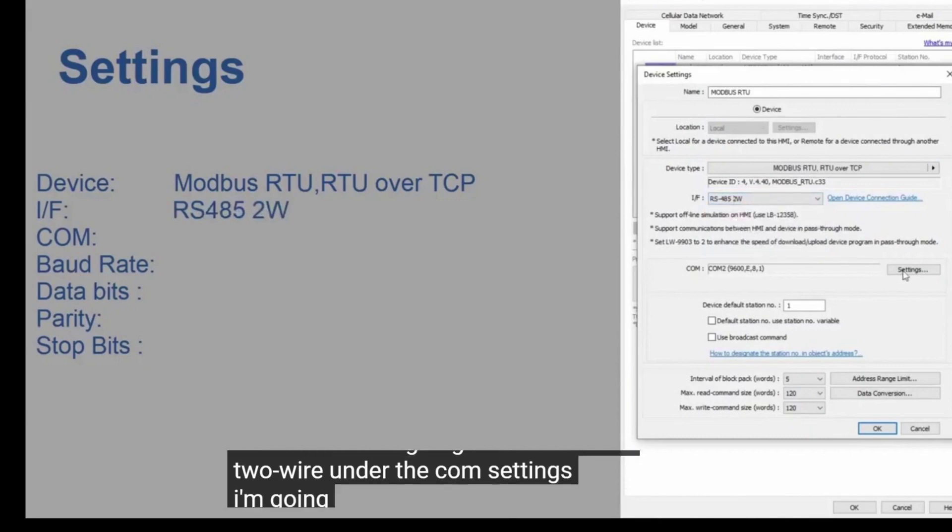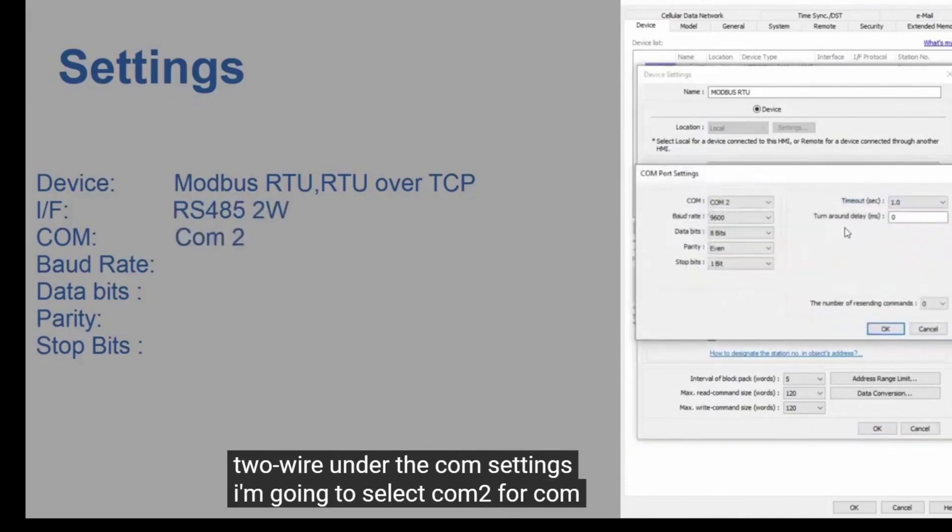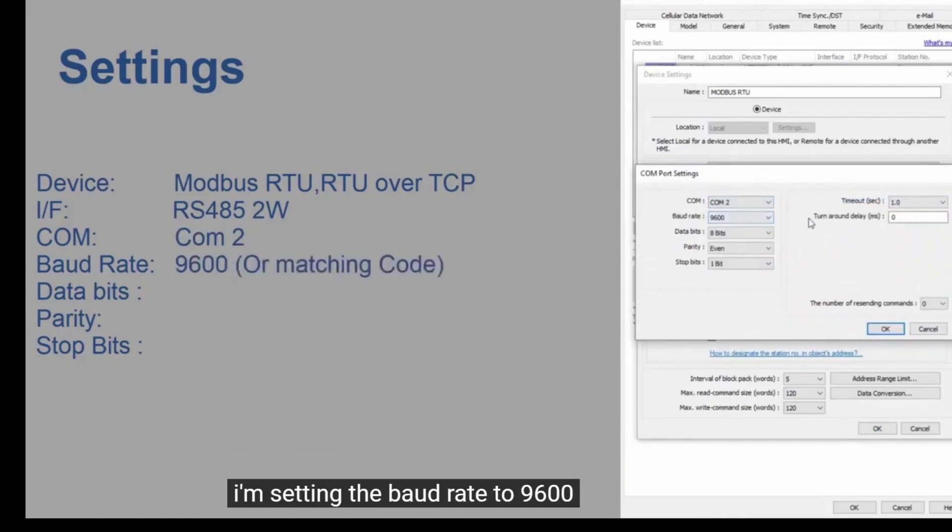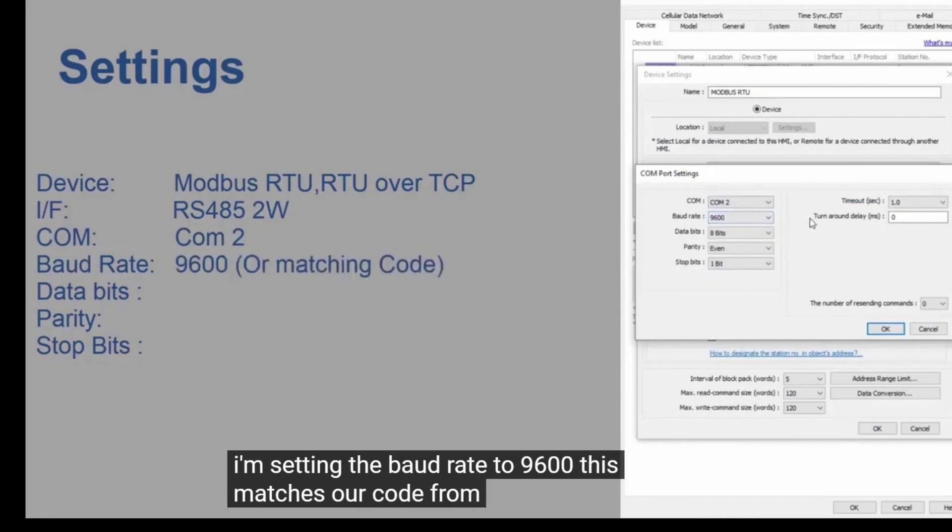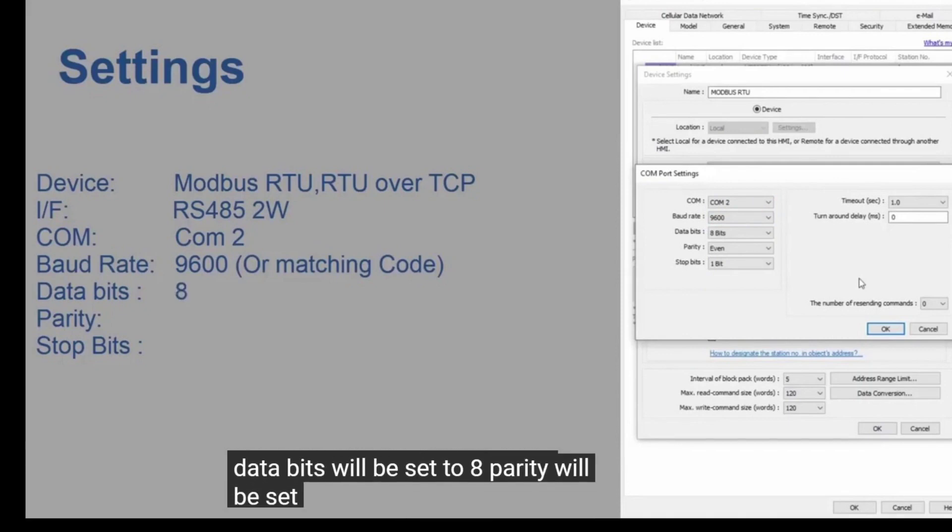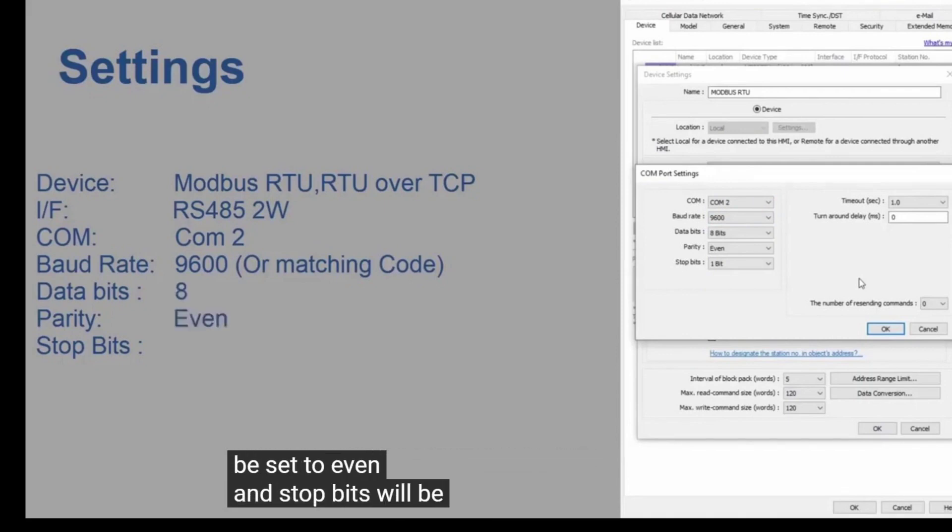Under the COM settings, I'm going to select COM2 for COM. I'm setting the baud rate to 9600. This matches our code from earlier. Data Bits will be set to 8, Parity will be set to Even, and Stop Bits will be set to 1-bit.